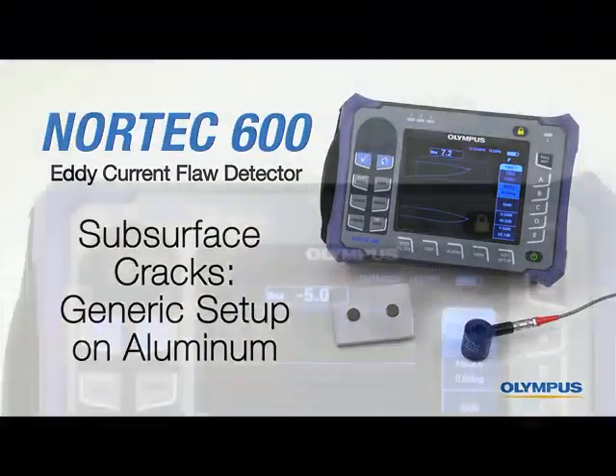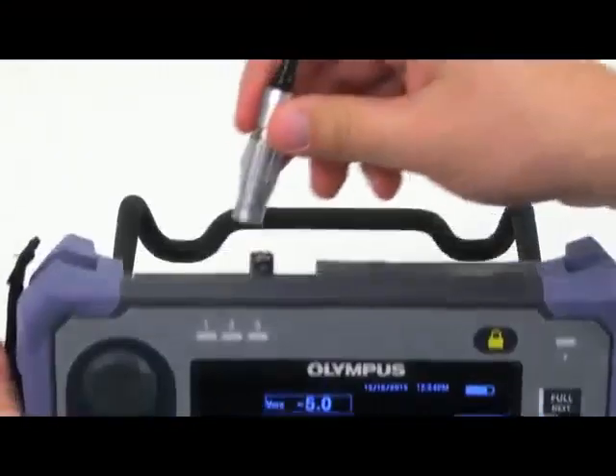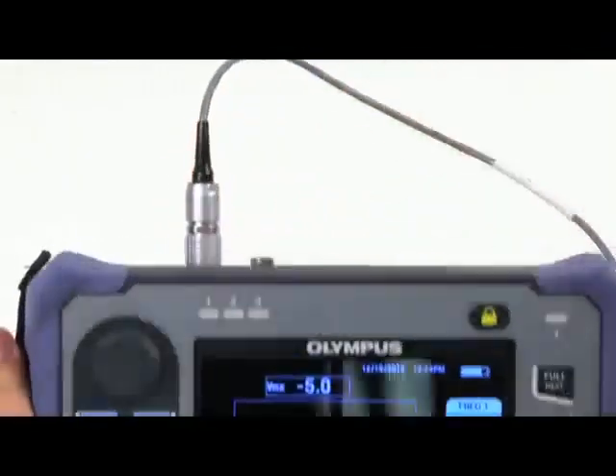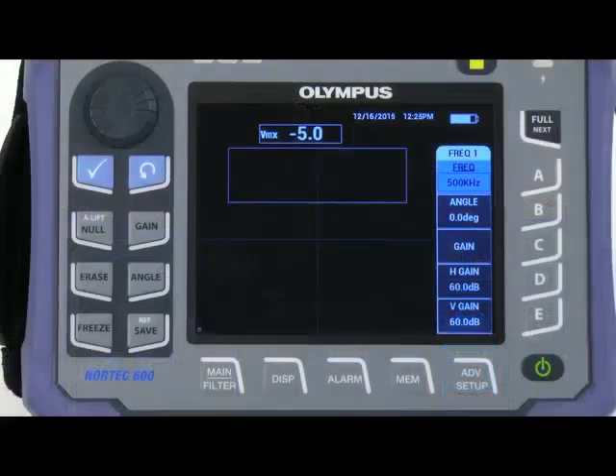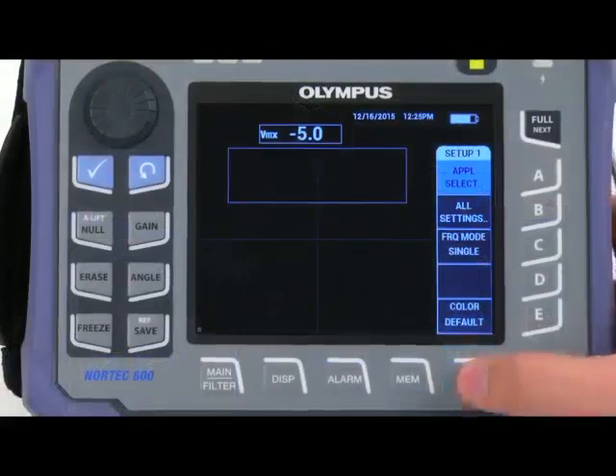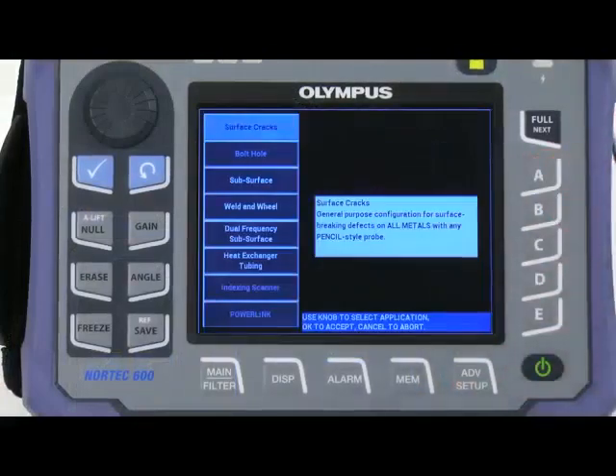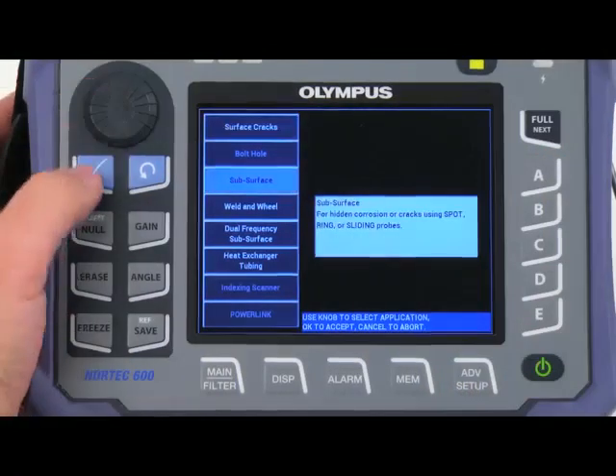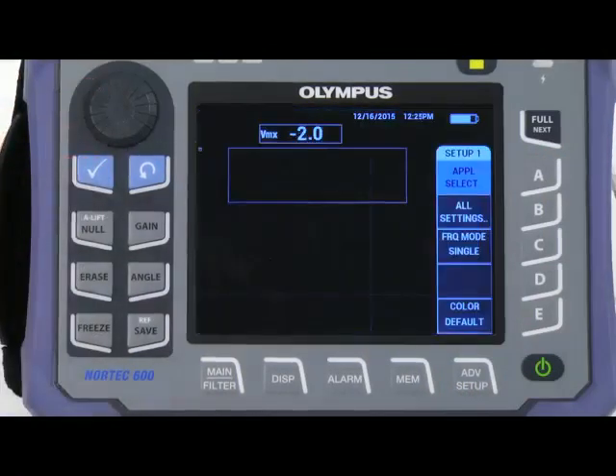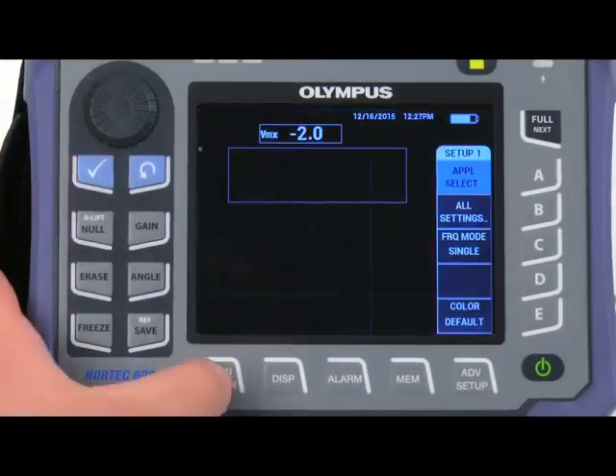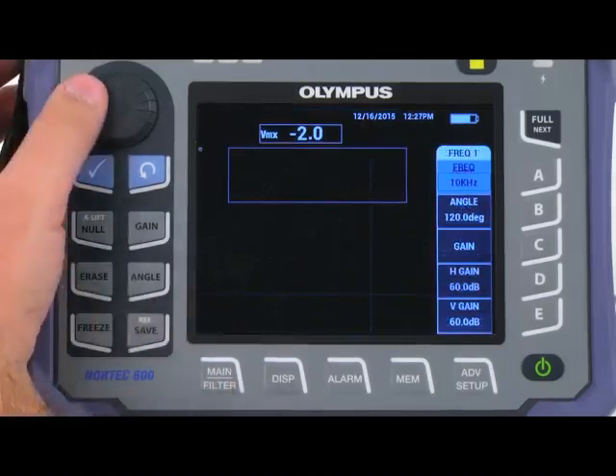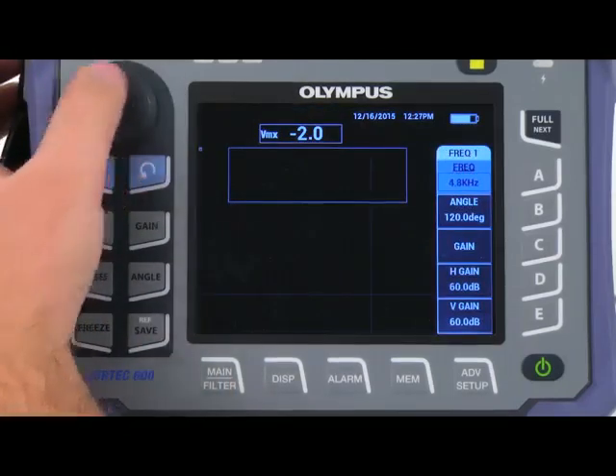For subsurface crack inspection, connect an appropriate probe to the N600. Press the Advanced Setup key, then Application Selection. Select Subsurface from the menu using the knob and press the checkmark key to accept. Press the main key to set the frequency. In this case, we know the correct frequency, and we will set it using the knob.